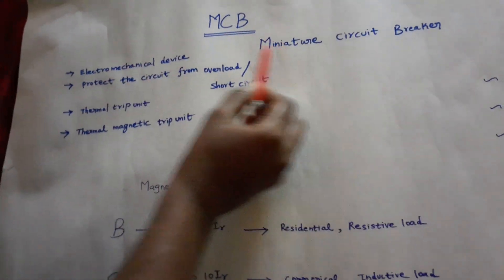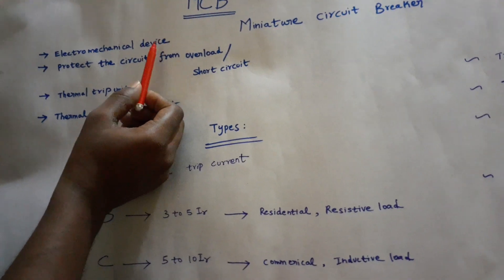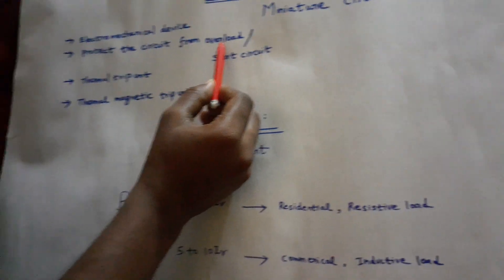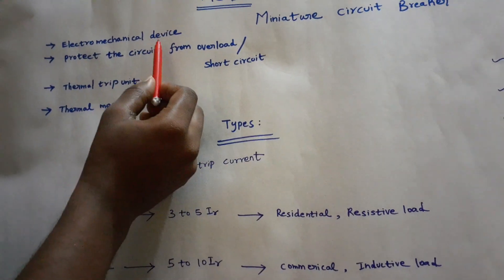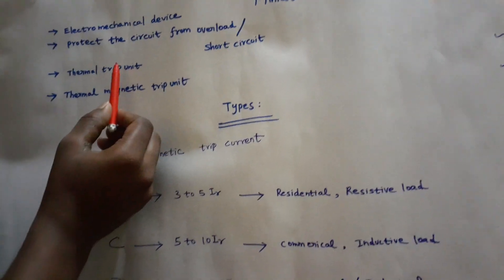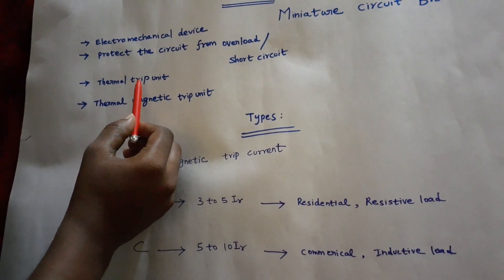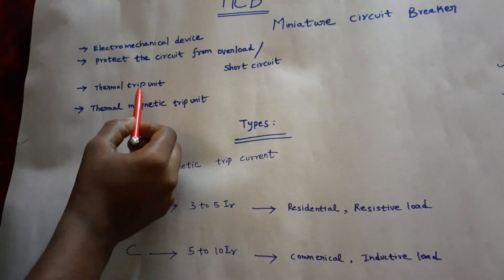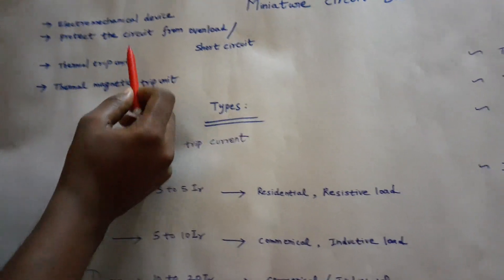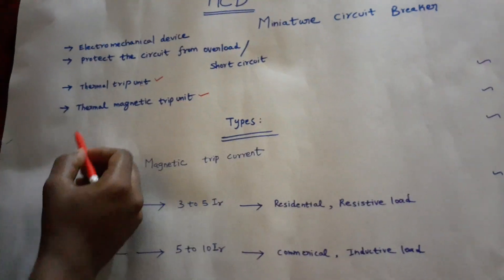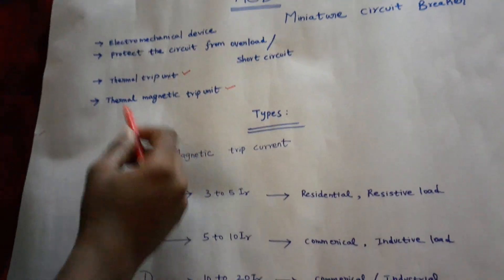MCB is a miniature circuit breaker. It is an electromechanical device. When placed in a circuit, it protects against short circuit or overload conditions. In MCB, there are two trip units: one is the thermal trip unit, which provides protection against overload, and the magnetic trip unit, which provides protection against short circuit.